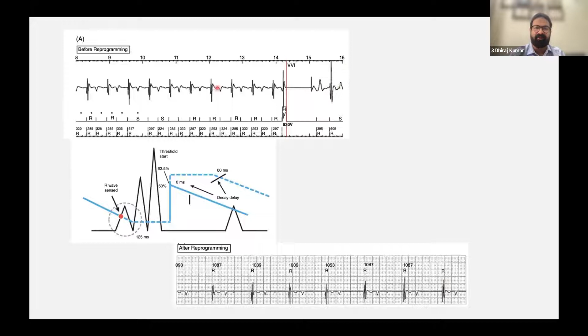Now, this decay may be programmable in some devices, and may not be programmable in other devices, but modern devices have T wave sensing algorithms which take into consideration, as I showed you earlier, the frequency and the amplitude both together, which is fed into the algorithm, and therefore it can recognize T waves very successfully. There is another thing that modern devices have: how closely matched this abnormal signal is to the preceding QRS, and then there is a gap. So the T wave has a particular way in which it occurs. It occurs at a fixed duration after the QRS, and then there's a longer duration. So if it is like that, then often T wave oversensing is avoided.